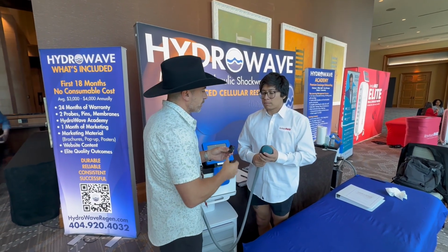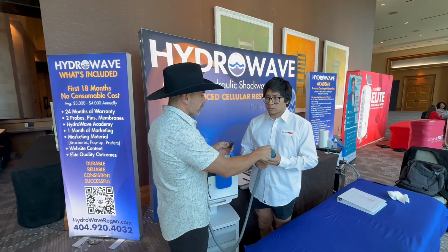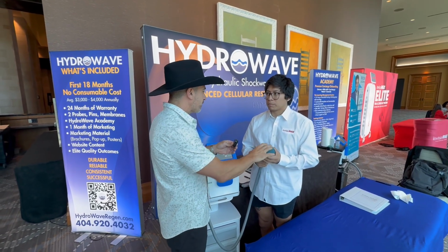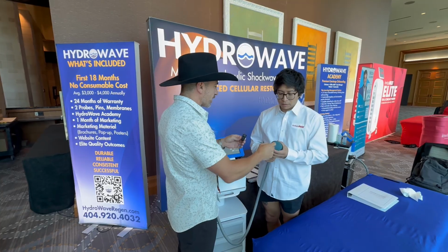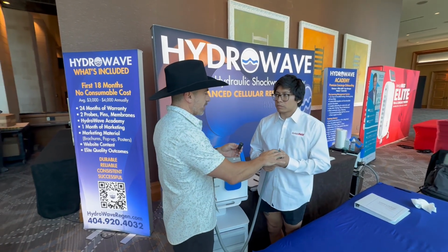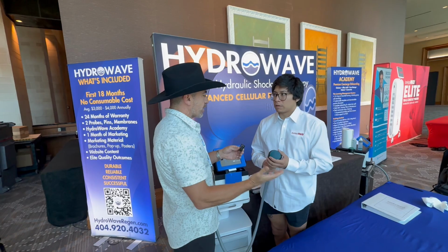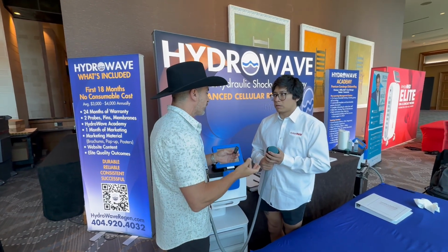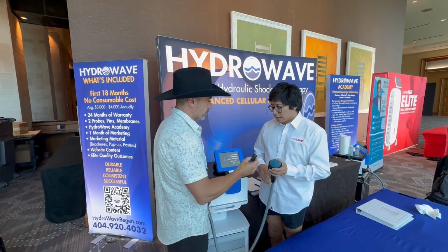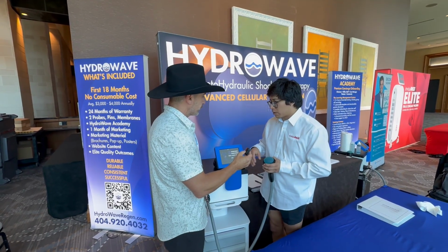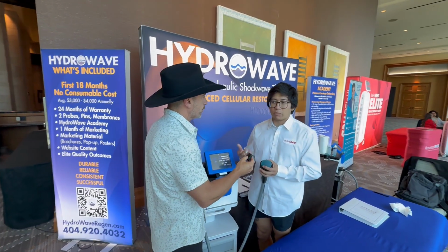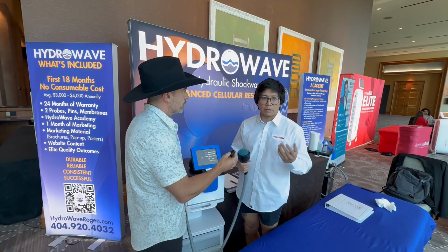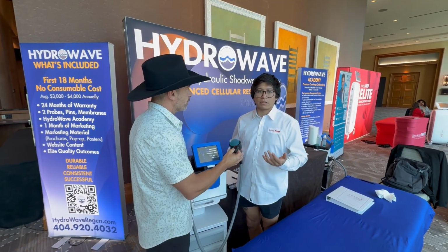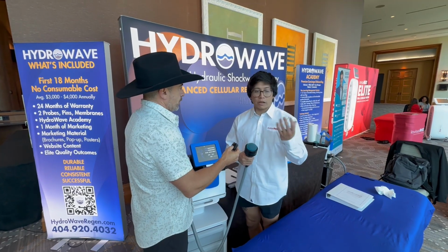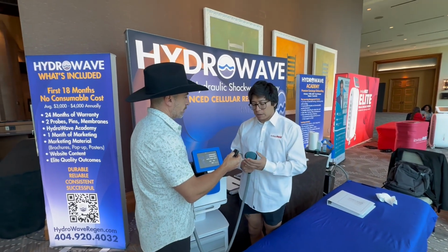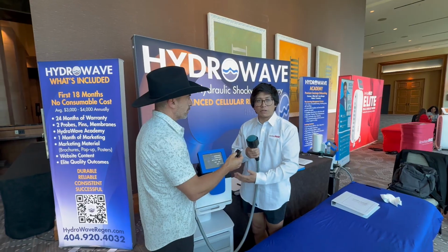Okay. And in some of the other devices, the membrane can be torn. It basically feels the same as the other ones, and sometimes these can have tears in them. Does this one still have the ability to tear, and how would you tear it? Yeah, a lot of times tearing it could be from something sharp, or you put too much pressure in it, or you tap it against something and it starts leaking. With other devices, you would either have to change the whole head out and get a new head in there. With Shockwave, you would have to get a whole new probe itself because you can't take it apart.